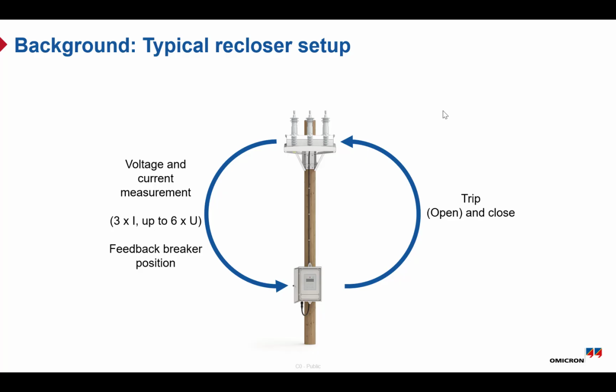First, we have the measurement signals. The controller receives three-phase current measurements and voltage measurements, which can be set up to 6 voltages depending on the setup. These signals come from CTs and VTs and are used for protection functions like overcurrent and voltage-based protection. Next, we have the status feedback signals. The controller needs to know the actual position of the breaker, so it receives open and closed status through auxiliary contacts, typically known as 52A and 52B.